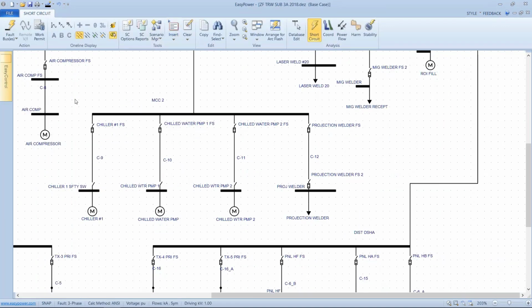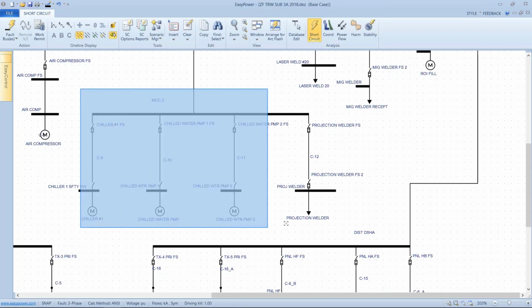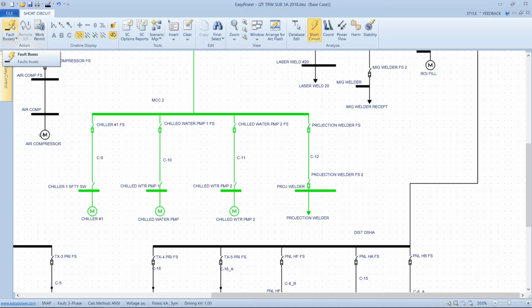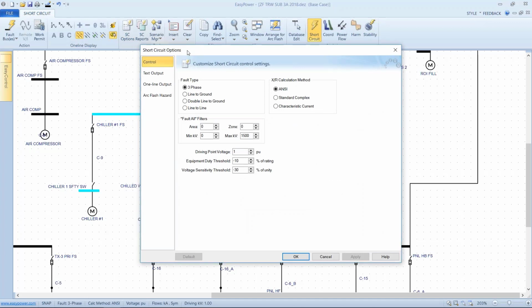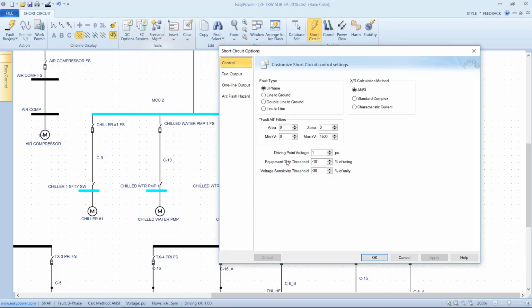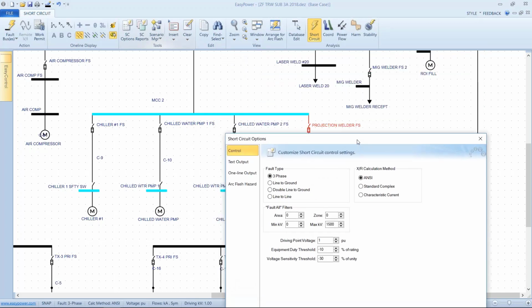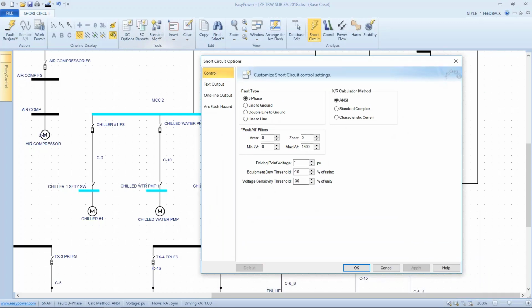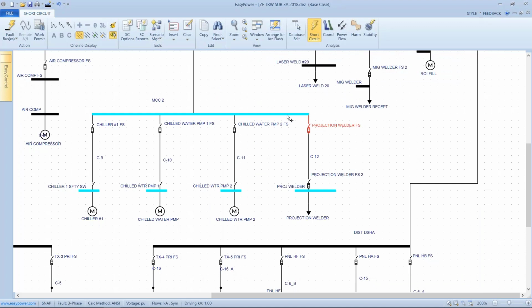So now when I go back to short circuit focus, I want to just look at this section of the one line. Let's fault the components, look at equipment duty. Now just for grins, for those of you that don't know, when I go to short circuit options, again, I'm in a short circuit focus, and I look at the control tab, this equipment duty threshold is going to turn the element red if it's within 10% of its equipment threshold. There are times that I may want to play with this number to allow me to see a broader span, and that comes into play, frankly, in motor control centers. So let's jump back into the presentation and talk about that.